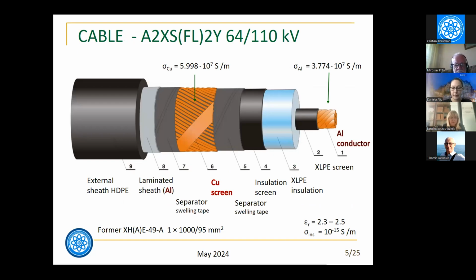This is a triple extruded power cable applying proprietary materials on modern catenary line equipment. The foil laminate layer provides an effective water and moisture barrier and produces a limited increase in mechanical protection. Nevertheless, it should be noted that this cable must be adequately protected from potential mechanical damage too. The cables are provided with a high-density polyethylene sheath selected to offer the best compromise between abrasion resistance and flexibility.